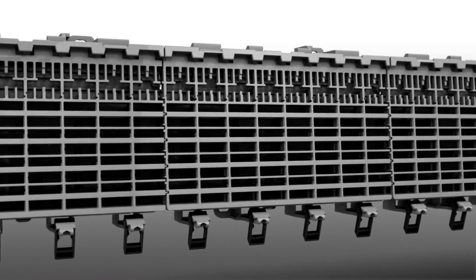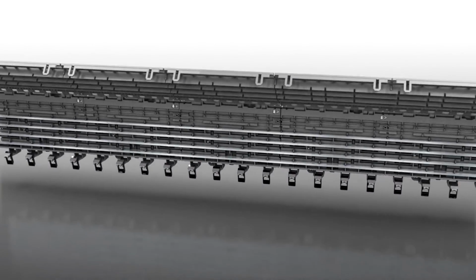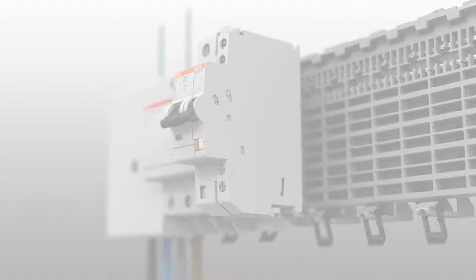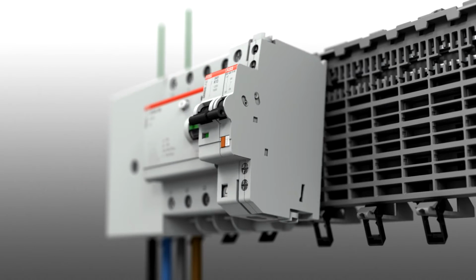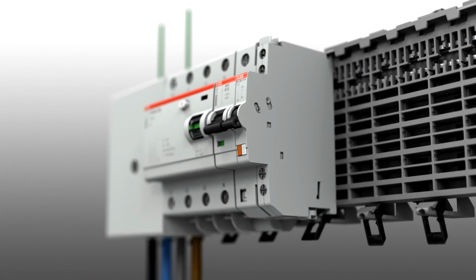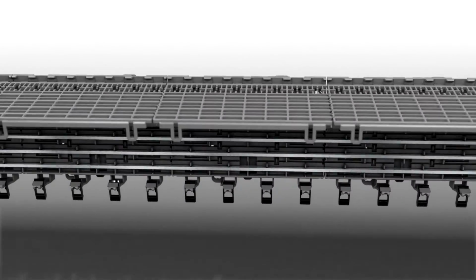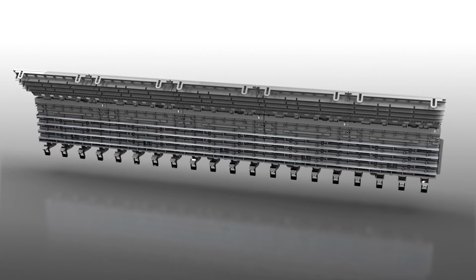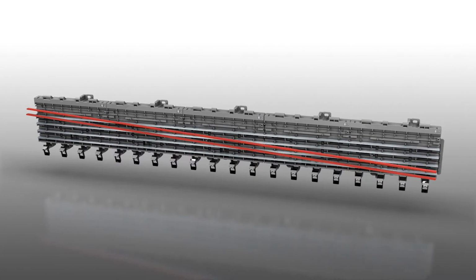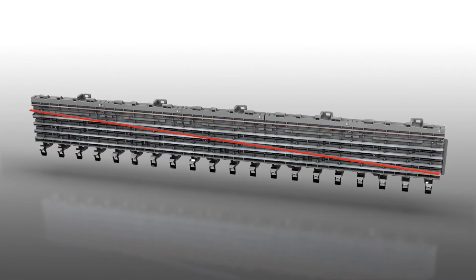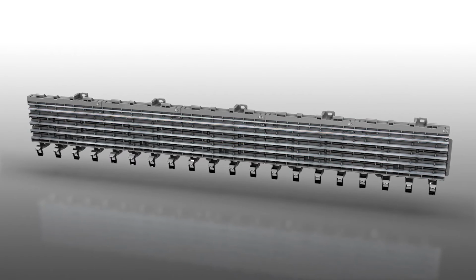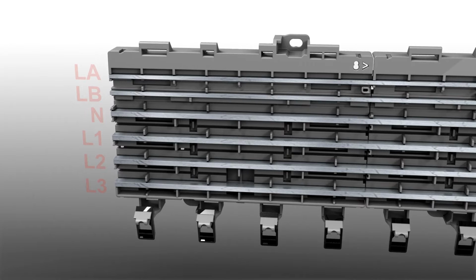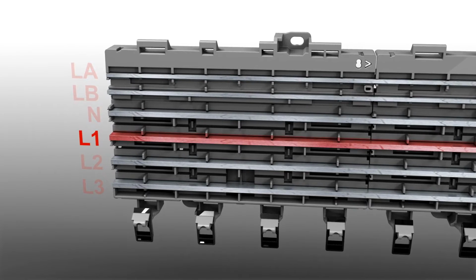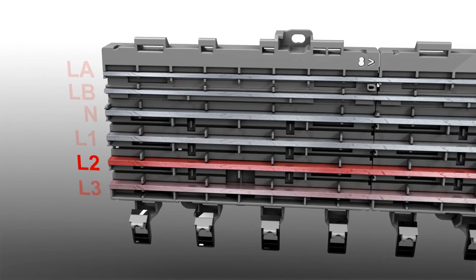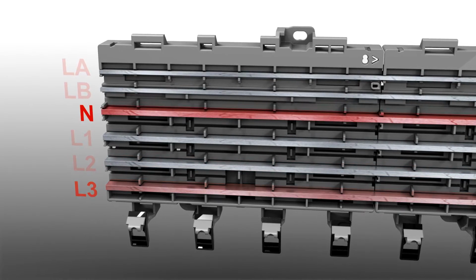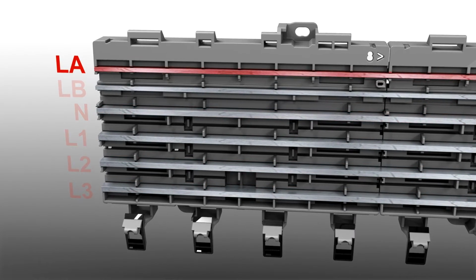Prefabricated starter kits make work easier because the sockets and bus bars are already joined together. This means that the devices can be fitted directly in place. However, the components can also be fitted together as easily as child's play. When doing this, the bus bars are inserted into the socket from the front. The following are provided: bus bars for external conductors L1, L2, L3, and the neutral conductor, and two auxiliary bus bars for the signaling.